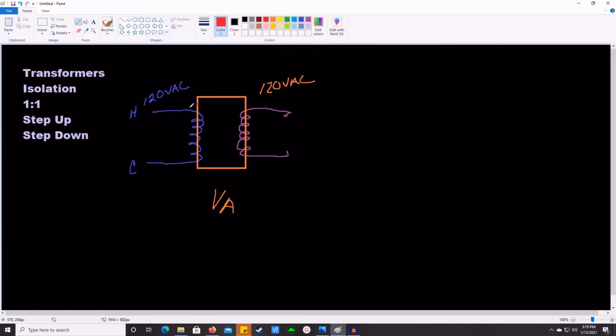Number one, your transformer won't work. But number two, it becomes unsafe. These wires are generally covered with an enamel, very thin, and when the transformer gets too warm, it can cause a breakdown on that enamel, especially if it's been bent too many times or wiggled back and forth. It really doesn't take much to wear through that enamel and give a path for electrons to flow, creating a closed circuit between the wire and the transformer. If we have that on both sides, it's a fire waiting to happen.